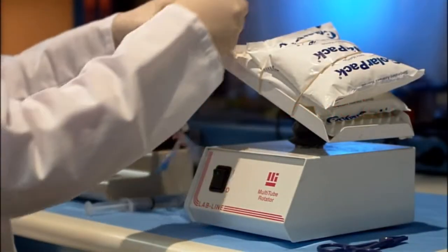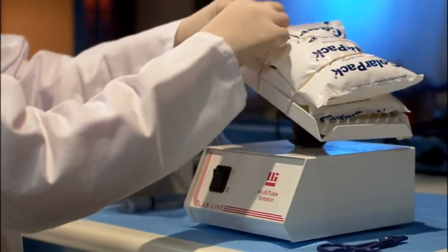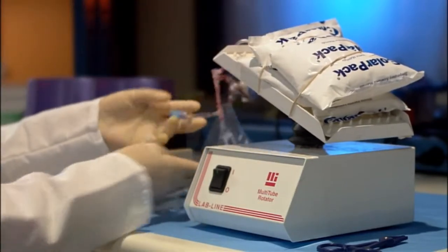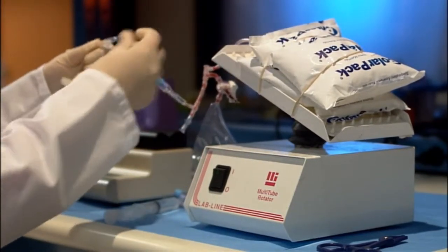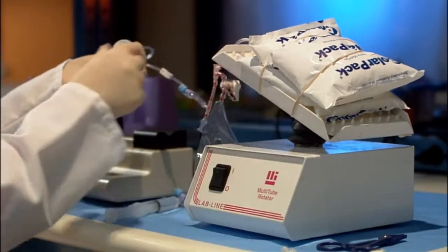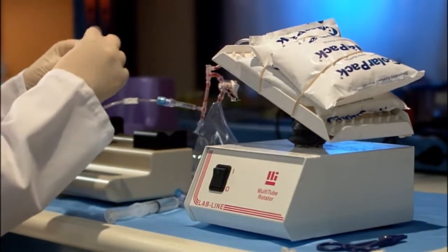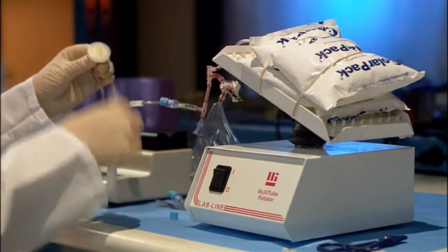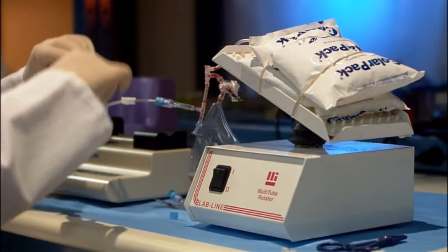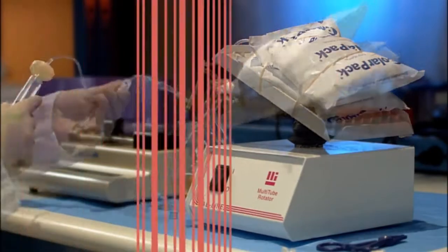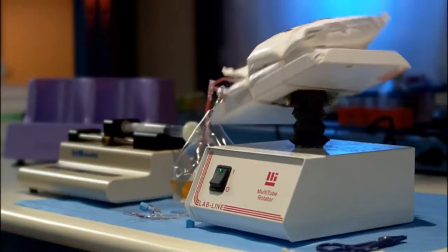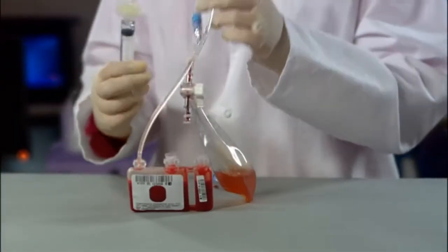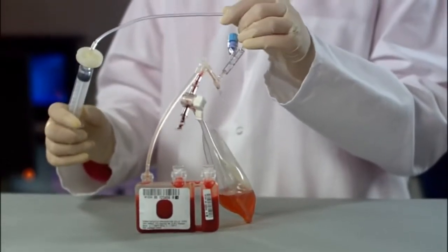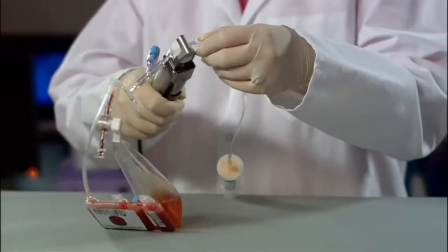Pre-chill the freezing bag containing the buffy coat to 2 to 6 degrees Celsius. Aspirate an appropriate volume of DMSO solution into a syringe and prime the DMSO line. Position syringe in the syringe pump and start adding the DMSO per your validated process. Heat seal and remove DMSO line.